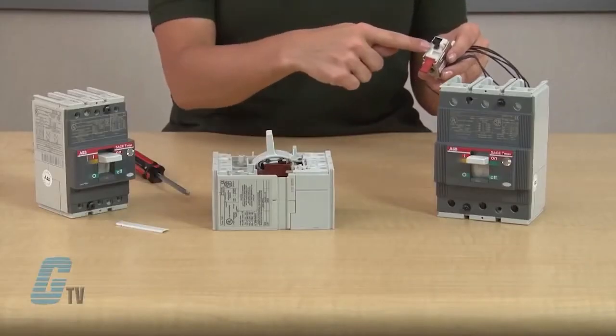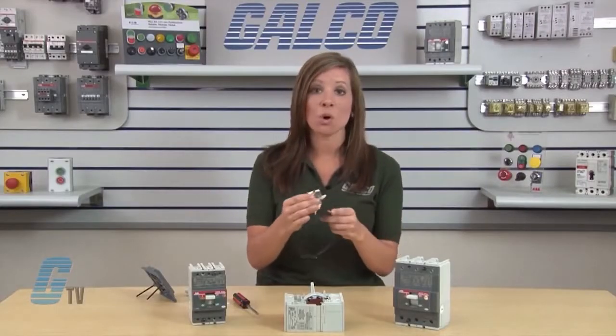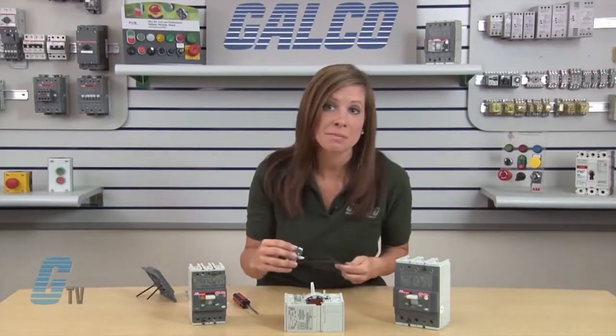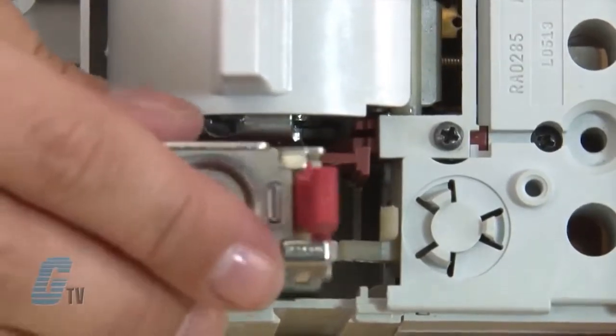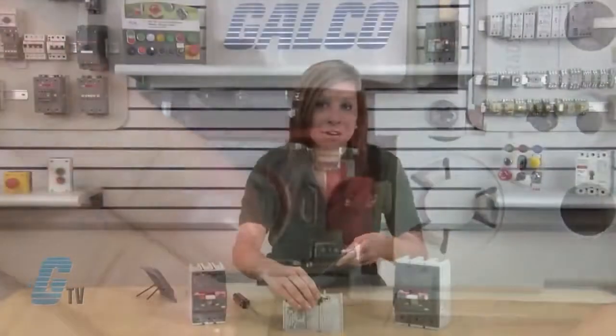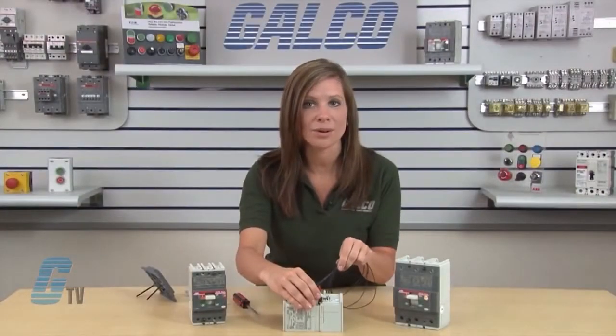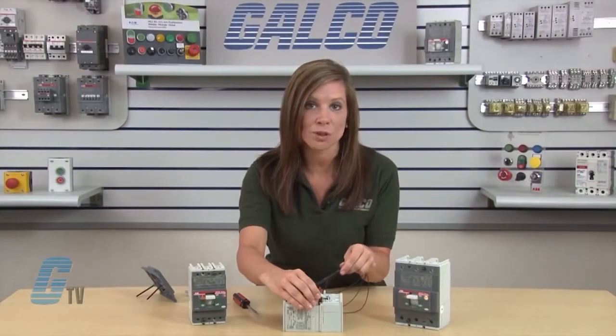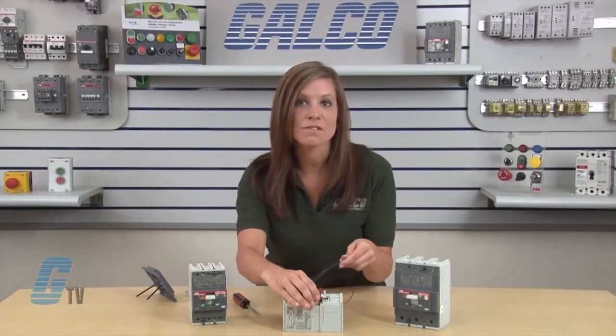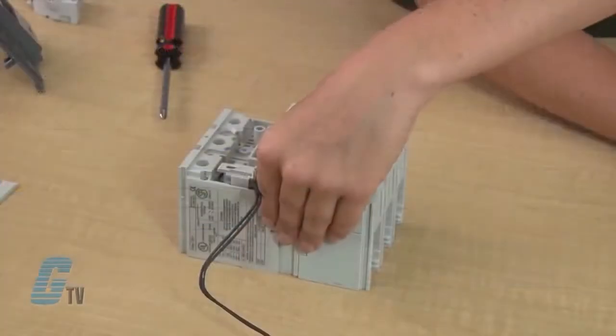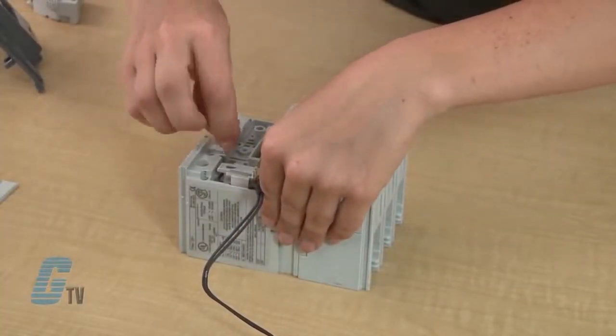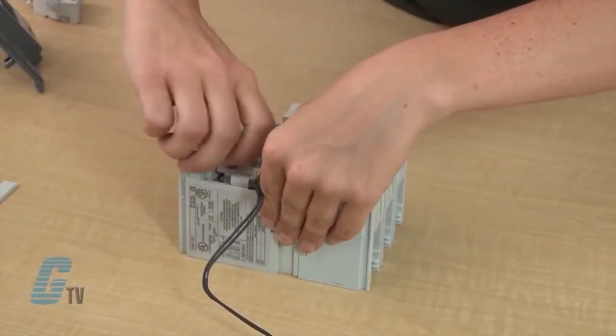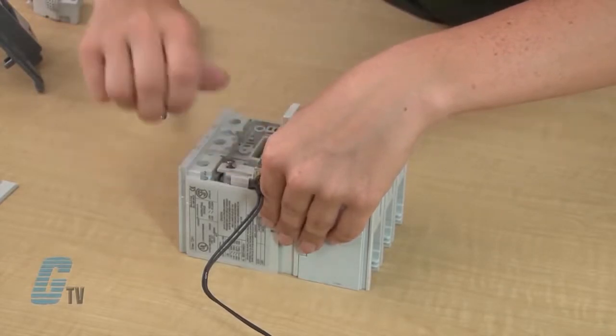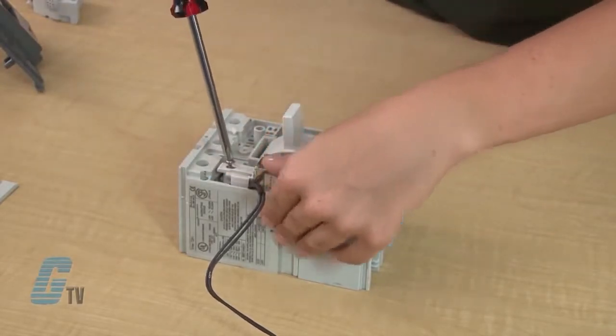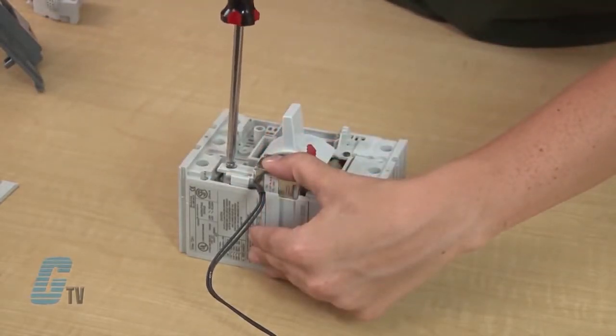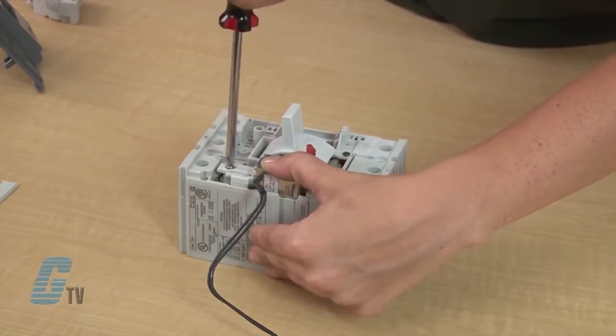I will install the UVR in the breaker by inserting this actuator tab into this opening at the back of the accessory port while aligning the hole in the UVR's mounting tab to the mounting hole on the frame. During the installation, I carefully make sure that the wires are routed in the narrow gap in between the UVR unit and the inside of the circuit breaker frame. During the installation, I feel slight resistance of the trip mechanism spring tension, pushing the trip unit out of position. So I keep pressure here with my thumb while fastening it with the screw.